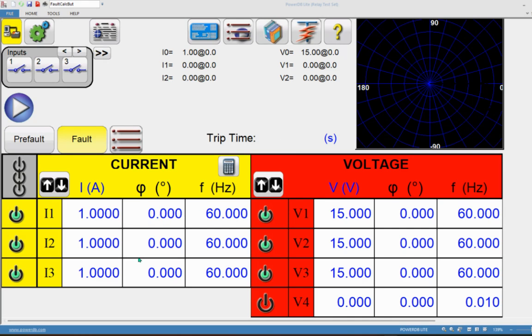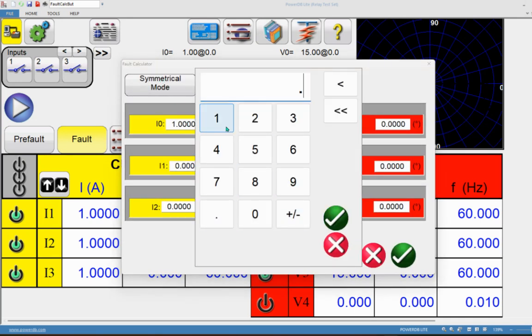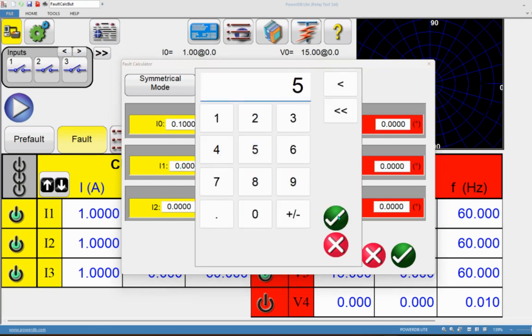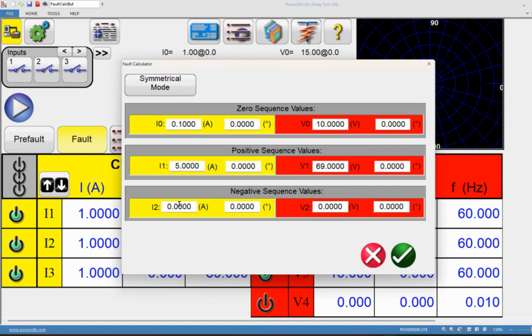The challenge comes when we want to generate a mixed voltage with a combination of positive, negative, and zero sequence values. Going back to the fault calculator: set zero sequence current to 0.1 amps and zero sequence voltage to 10 volts; positive sequence voltage to 69 volts and positive sequence current to 5 amps with no phase angle difference; negative sequence current to 0.5 amps with a phase angle of 30 degrees; and negative sequence voltage to 15 volts.